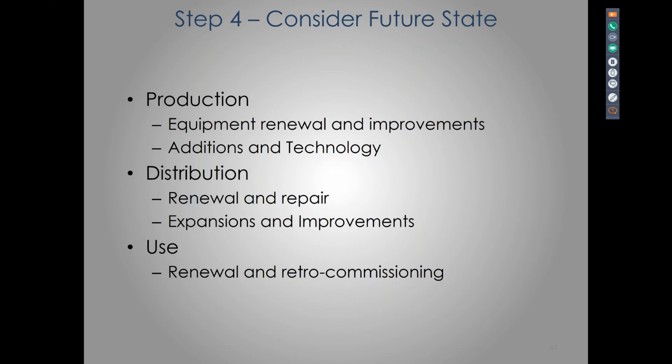Recently, a technology change here was going from very large scale water tube boilers to much smaller scale but very quick reacting, low mass boilers that made a large difference in the amount of residual heat when the loads bounce up and down. We're able to follow them very quickly. A technological change. 10, 15 years ago, we probably couldn't have done that. Now it's available. Apply that technology and instantly reap the return.